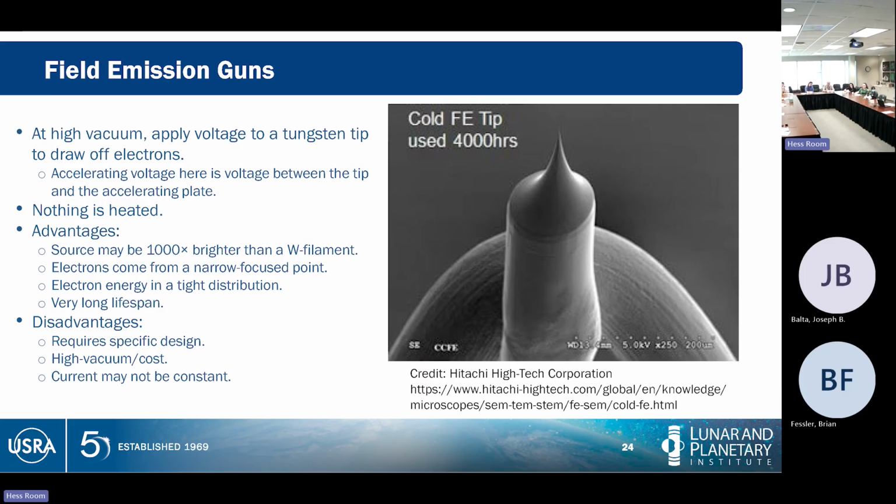To find these, you will find these mostly in your floor models, because making these work well requires operation of vacuum systems, operation of maintenance systems. So if you're going to spend the money on putting one of these things in, where you need the extra resources, this is the place where you put all the bells and whistles. The extra detectors are often on this design.